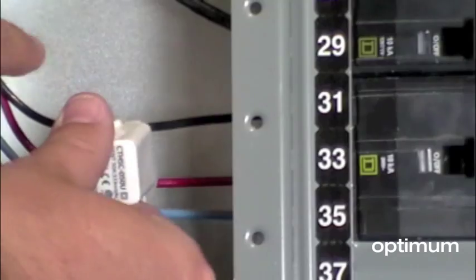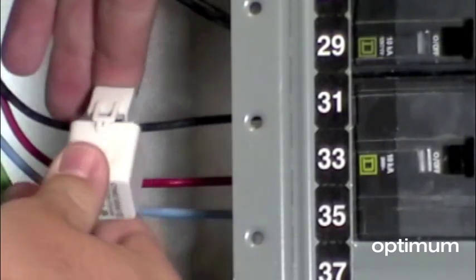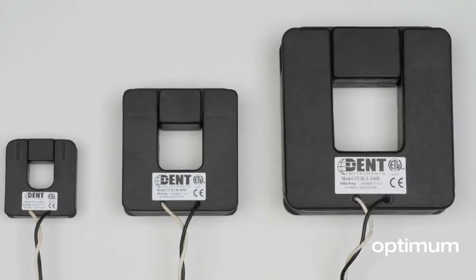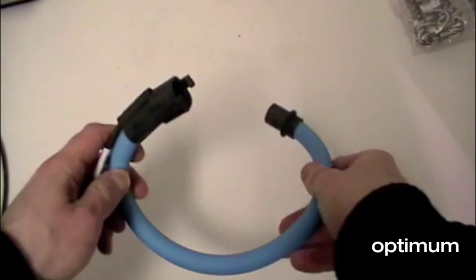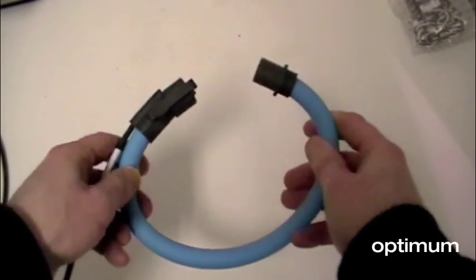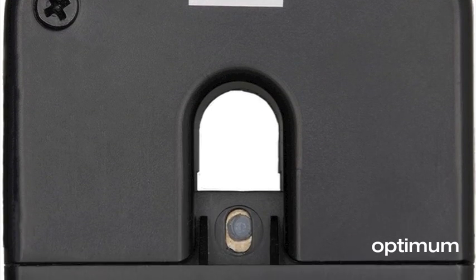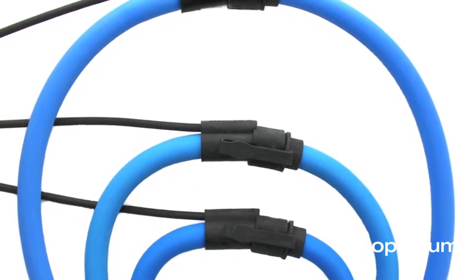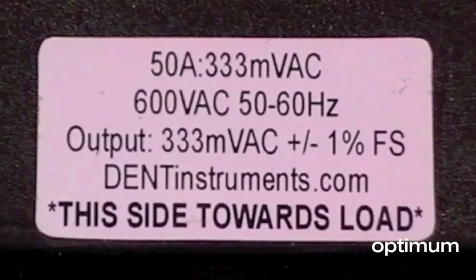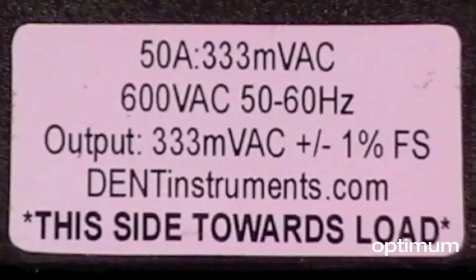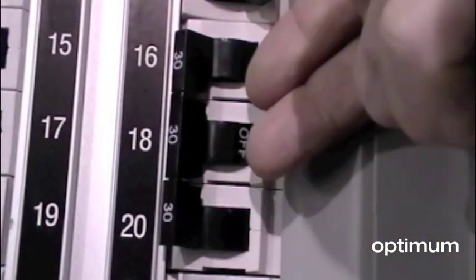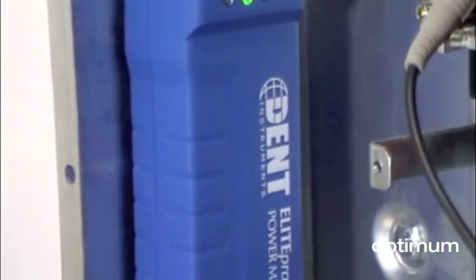Third, the ELITEpro SP works with a huge choice of interchangeable CTs to meet your specific project requirements. Choose from split core, clamp on, or flexible Rogowski style current transformers. CTs are available for loads ranging from 5 amps up to 6,000 amps. All Dent CTs feature millivolt output signals, so they can even be installed without shutting the power off. All this in the industry's most versatile, compact, and cost-effective energy data logger.